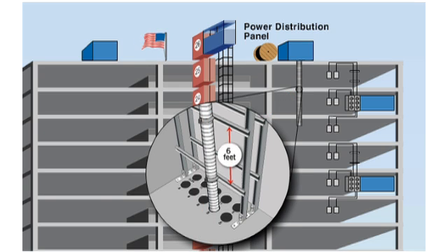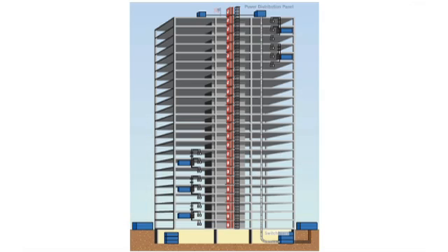Because riser MC cable is listed as a type MC cable, it must be supported and secured externally every six feet. Southwire's riser MC cable is manufactured using AlumaFlex 8000 series conductors and is currently available in sizes ranging from 3-0 through 750 kcmil.